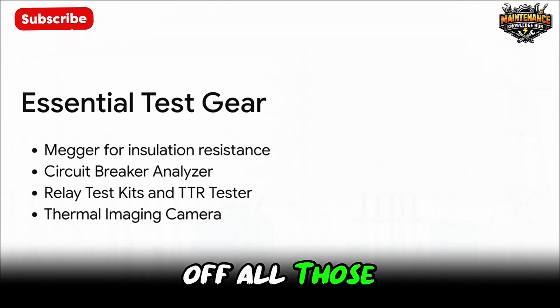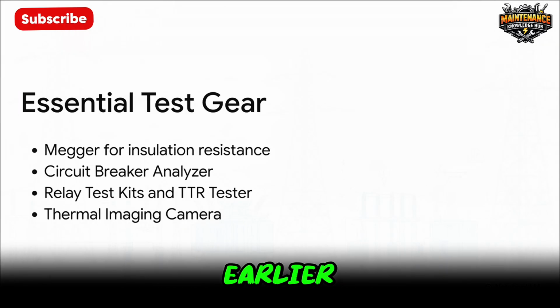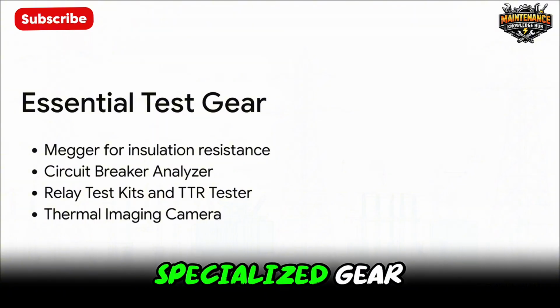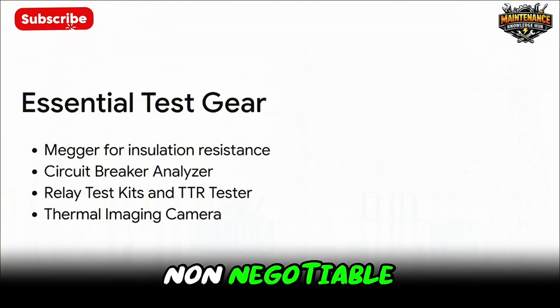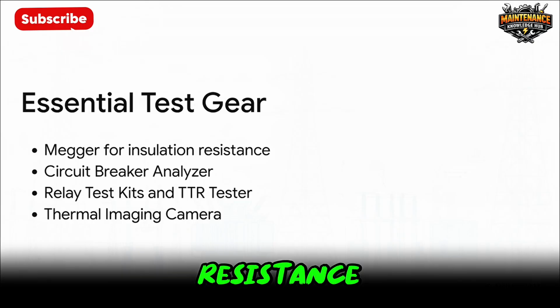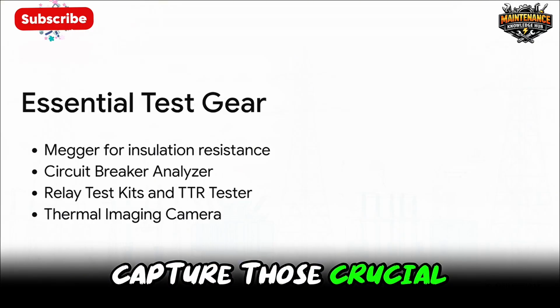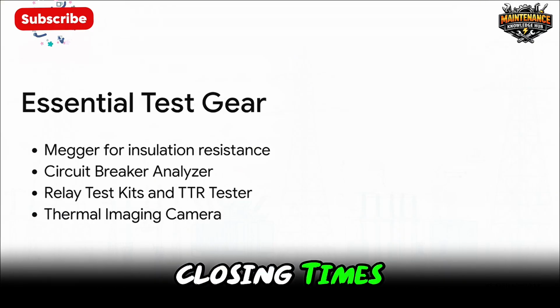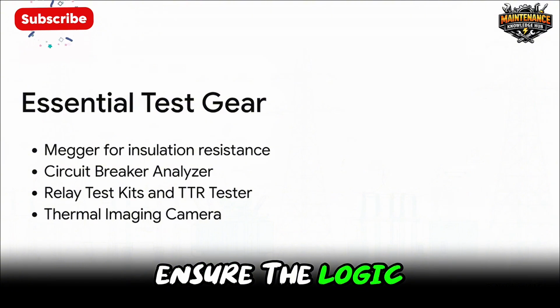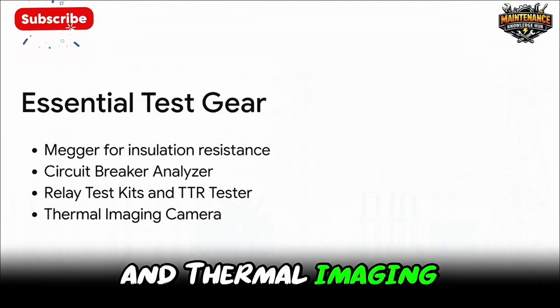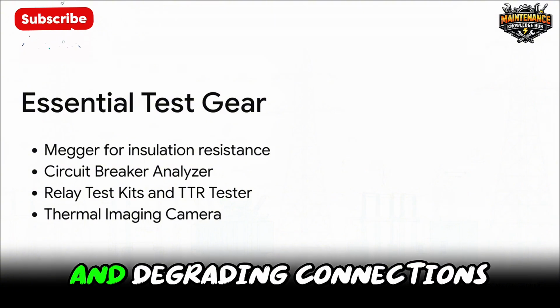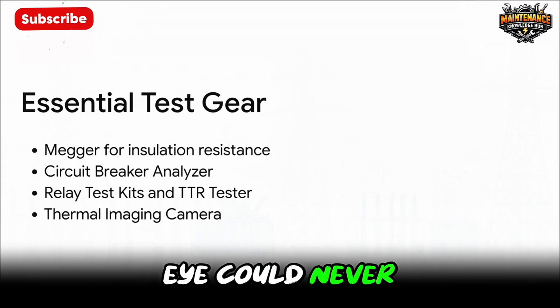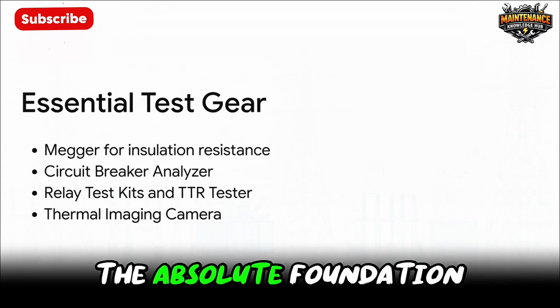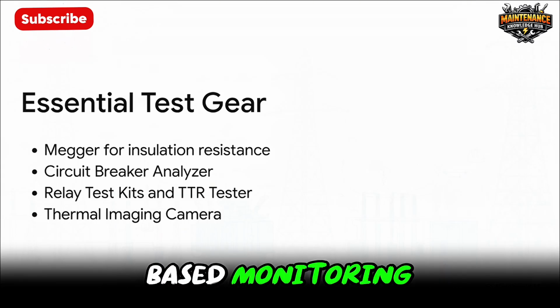And to pull off all those advanced diagnostics we talked about earlier, technicians rely on specialized gear. A Megger is non-negotiable for testing insulation resistance. Circuit breaker analyzers capture those crucial millisecond opening and closing times. Relay test kits ensure the logic pathways are sound. And thermal imaging cameras, they reveal hotspots and degrading connections that your naked eye could never see. This equipment is the absolute foundation of condition-based monitoring.